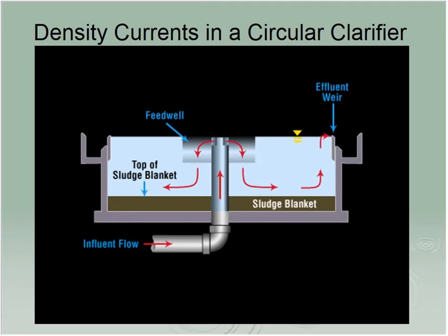The other thing that we're going to do here is maintain a sludge blanket, a layer of solids at the bottom of the tank. Two reasons for that. As material comes down and keeps settling, it compresses and concentrates. So if I've got mixed liquor of 2,800, I'm probably running 5,500 to 6,000 on my sludge at the bottom of the tank. So my pump to send return material back to the reactor is smaller because it's concentrated. And my pumping out to waste is smaller also.